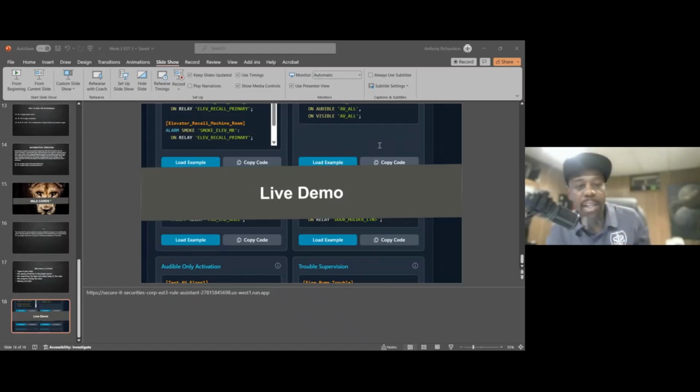And then you have relay configuration. You will use relay configuration usually for things like dampers. When the relay goes active, it will send a confirmation, so that you can take that confirmation and either do something else with it or turn something else on. Usually you take that relay confirmation and then control either fans or dampers after that.